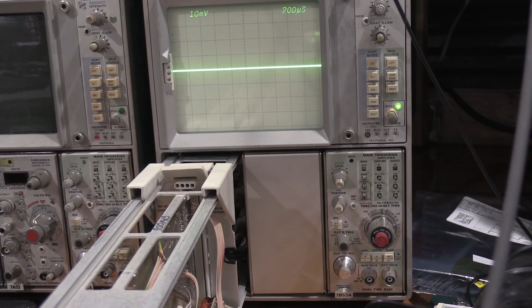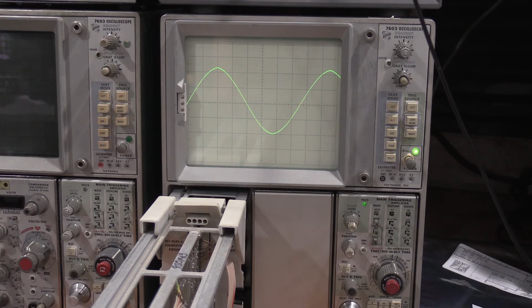Okay, on the spring that I fixed, it looks like I just had a little too much spring tension, and it was causing an intermittent contact on the other side. So everything's stable. I'm going to let it run and warm up. Don't want to burn in the screen. I'll make sure the trace is stable and doesn't go away. And if that is stable after a couple hours, I'll try to do a calibration on it and see what's going on. But I think we brought this plug-in back to life. I was hoping it was an electrical issue, but it ended up being a mechanical issue. That is sometimes the way it happens. So I will let that run and see if there's any more work to do.